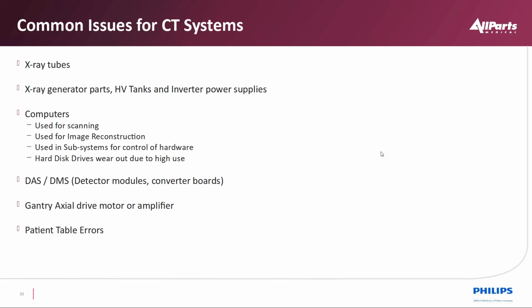Along with that, obviously, we're dealing with high voltage arcing because we have a vacuum inside that tube. Maintaining that vacuum is hard. We also have other issues with the rotor itself. We're trying to dissipate that energy with a rotating anode. The bearings wear out. Remember, we're slinging it around the gantry at high G's as well.